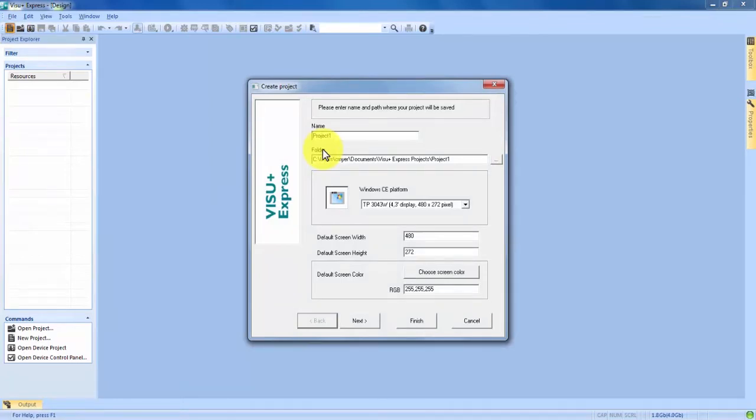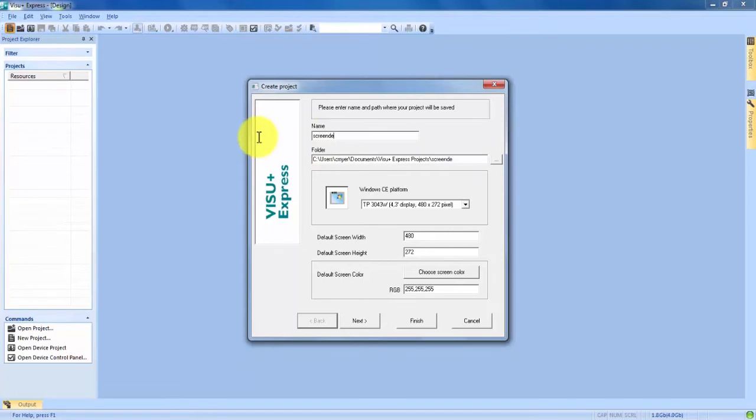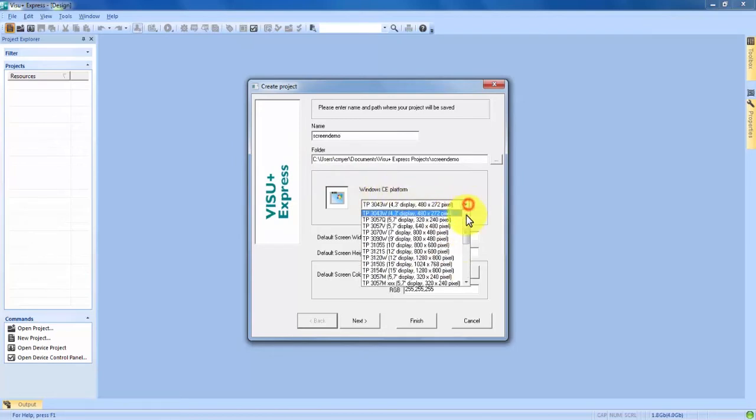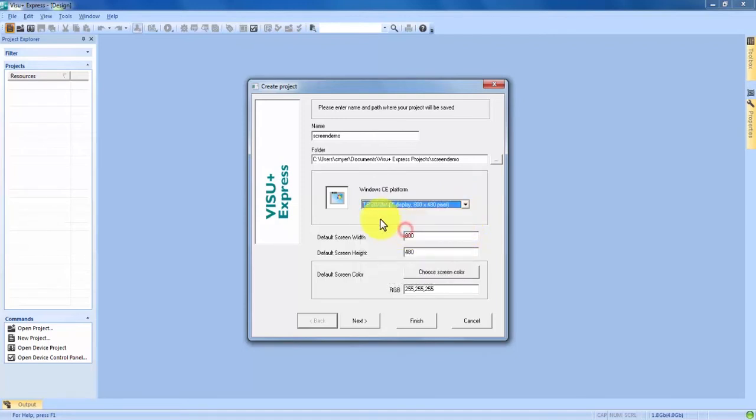Once we have the wizard open we have our first screen which is the main create project screen. Here we can choose some basics for the project. We can name it. I'll just name it screen demo for this purpose. Under that you get to choose your Windows CE platform which is going to be the HMI that you're exporting to. I'm using a 7 inch display so I'm going to choose the TP 3070W but you can choose whatever you're going to be using. Once you choose your CE platform it's going to default the screen width, height and color so you don't have to worry about changing that.